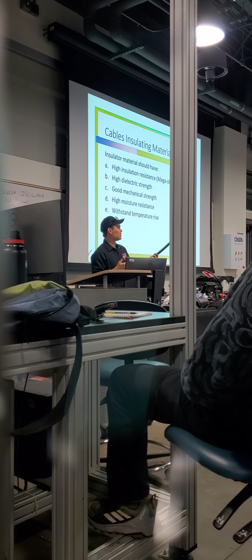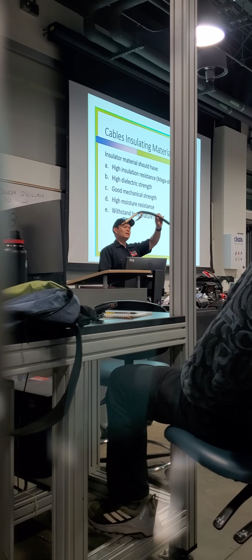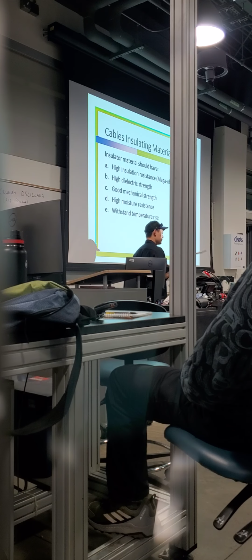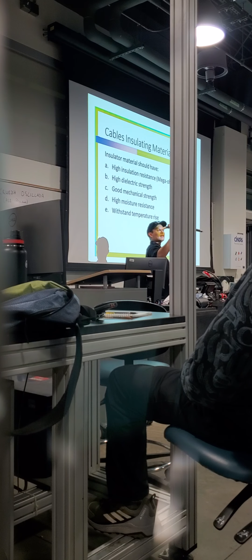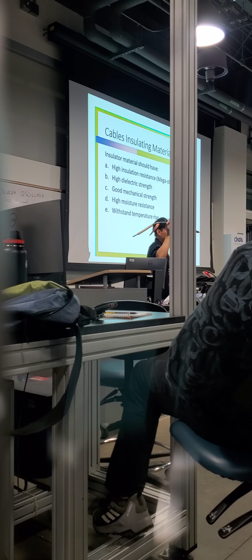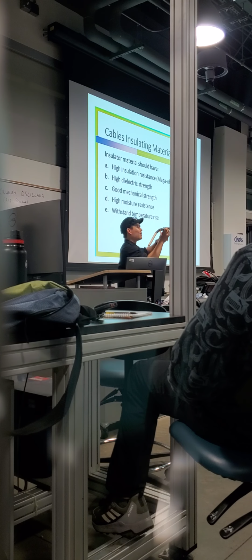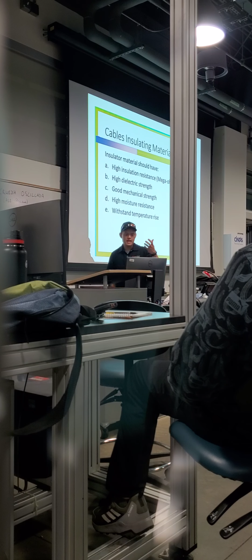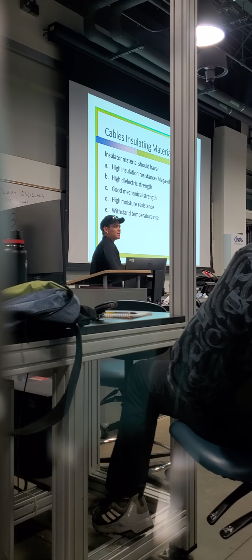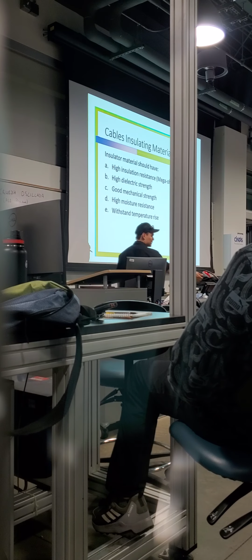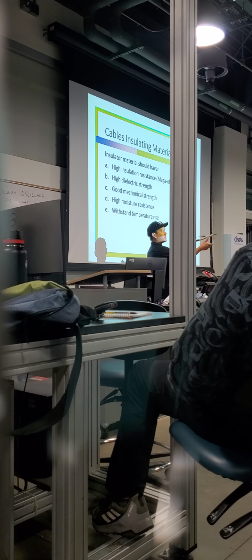We've seen those handheld meters that only go up to 1 kV. Do we think that's going to cut it? Not quite, because you're not getting any valuable information. Remember the familiar industry expression: garbage in, garbage out. If you have a little Harbor Freight meter to test this, you go to the customer looking all stoked saying the test numbers look great with my Harbor Freight meter. For something like this, they might give you a weird look and say, all right, next contractor on the list. So in this case, again, know the equipment you're testing, because that's going to dictate your test parameters, your test kV, for example. And hopefully, as you pass these around, you're already recognizing the points at which you're going to connect the leads.